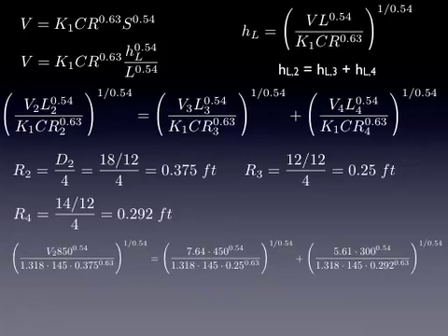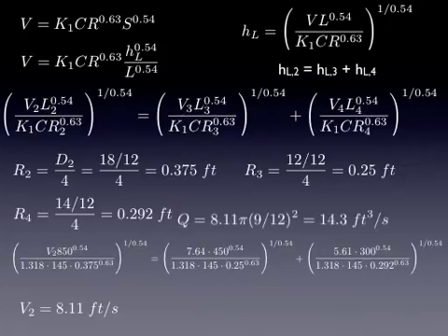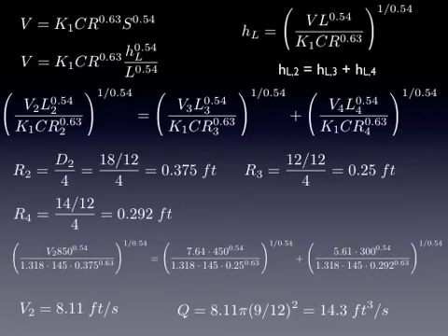So I've got V2 times the length of pipe raised to the power of 0.54 divided by my unit factor, divided by C, divided by the hydraulic radius raised to 0.63. And then I have to do the other exponent, sum that all up, and I get a velocity of 8.11. I can easily convert that to a flow rate.